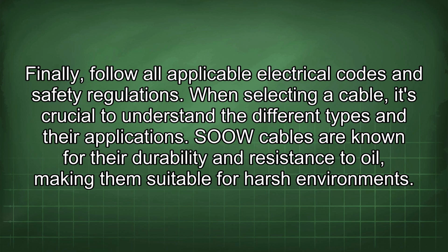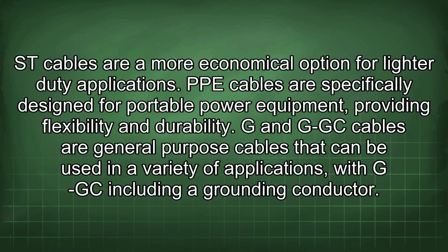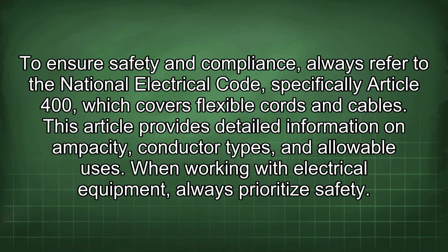When selecting a cable, it's crucial to understand the different types and their applications. SOOW cables are known for their durability and resistance to oil, making them suitable for harsh environments. SJ cables are a more economical option for lighter-duty applications. PPE cables are specifically designed for portable power equipment, providing flexibility and durability. G and GGC cables are general-purpose cables that can be used in a variety of applications, with GGC including a grounding conductor. To ensure safety and compliance, always refer to the National Electrical Code, specifically Article 400, which covers flexible cords and cables. This article provides detailed information on ampacity, conductor types, and allowable uses.